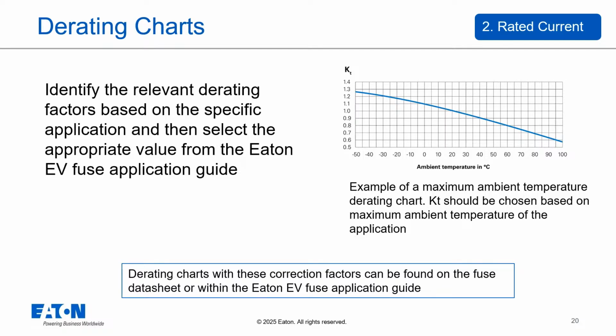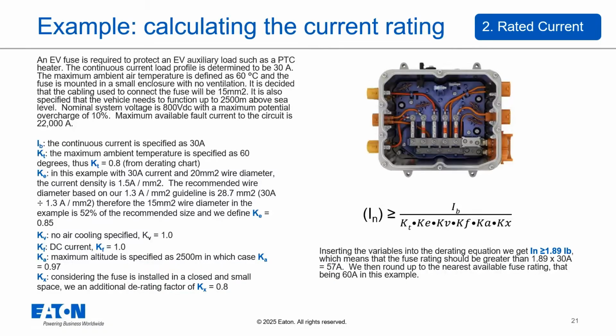Let's walk through a quick example to make this more clear. Suppose we need a fuse for an EV aux load like a PTC heater. The continuous current, I sub B, is 30 amps. Maximum ambient temperature is 60 degrees C. The fuse is in a small enclosure with no ventilation and is connected to cabling, which is 15 millimeters squared in cross-sectional area.